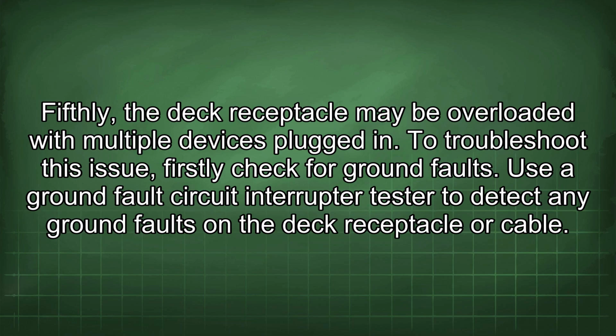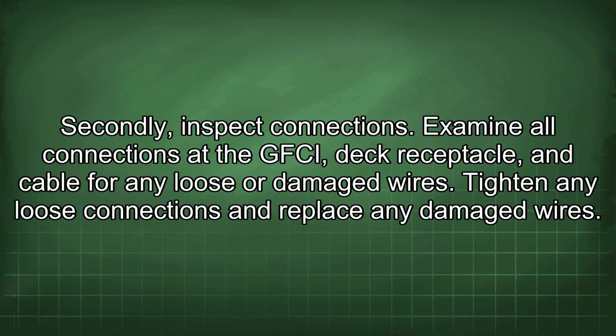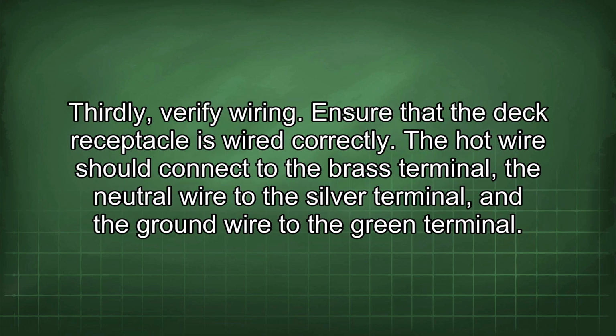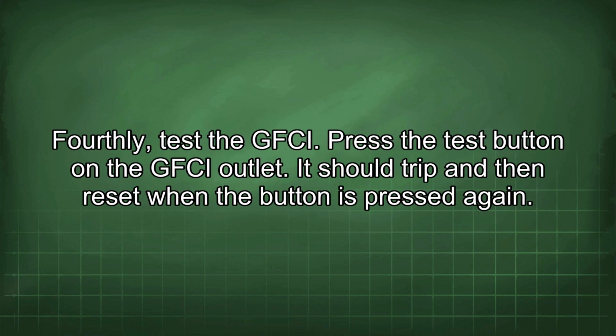To troubleshoot this issue, firstly check for ground faults. Use a ground fault circuit interrupter tester to detect any ground faults on the deck receptacle or cable. Secondly, inspect connections. Examine all connections at the GFCI, deck receptacle, and cable for any loose or damaged wires. Tighten any loose connections and replace any damaged wires. Thirdly, verify wiring. Ensure that the deck receptacle is wired correctly. The hot wire should connect to the brass terminal, the neutral wire to the silver terminal, and the ground wire to the green terminal. Fourthly, test the GFCI.